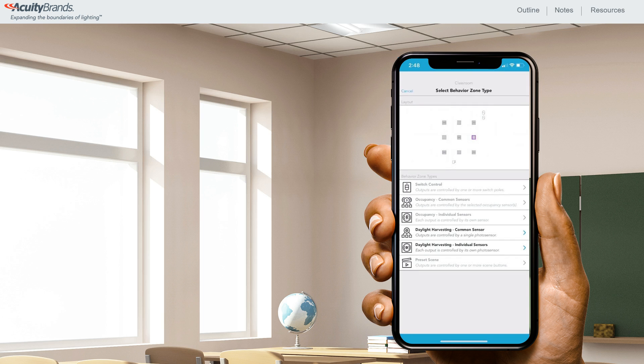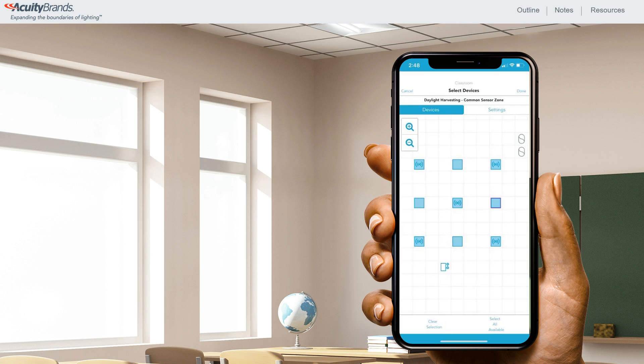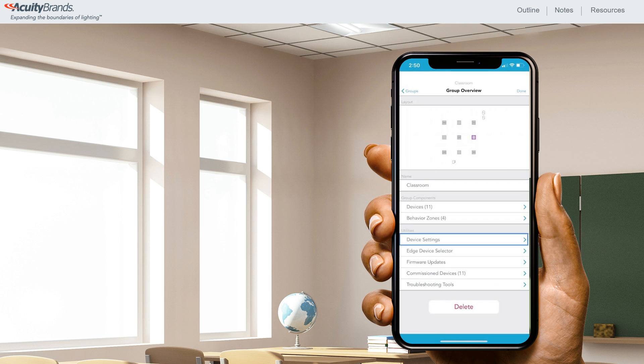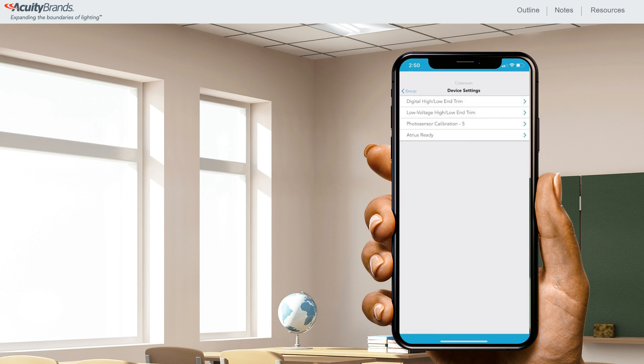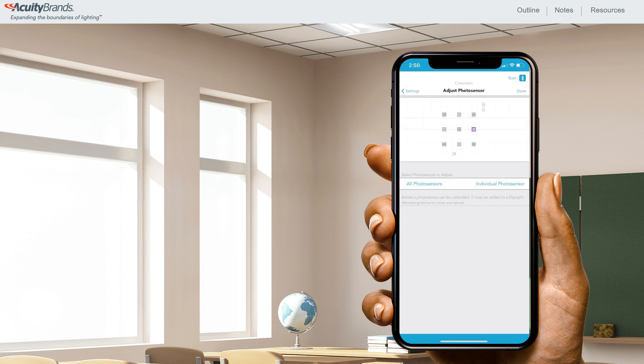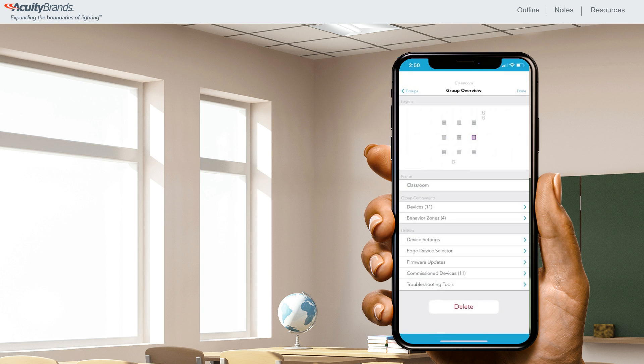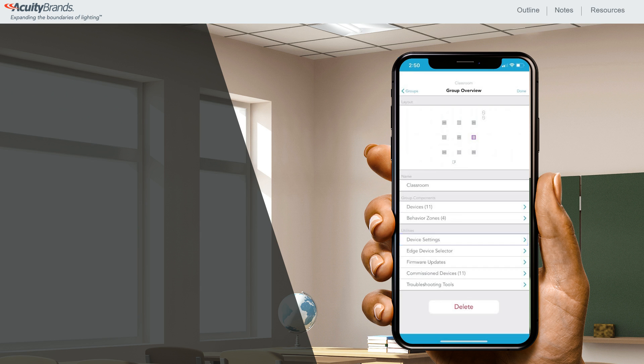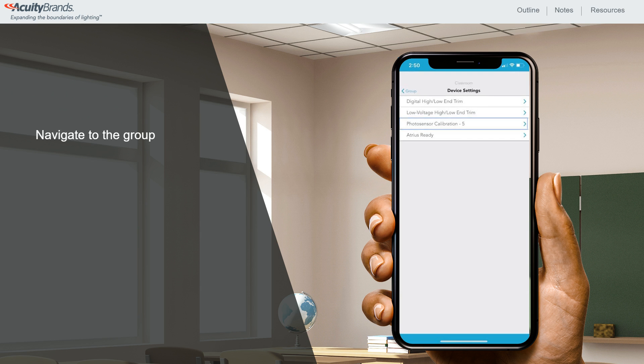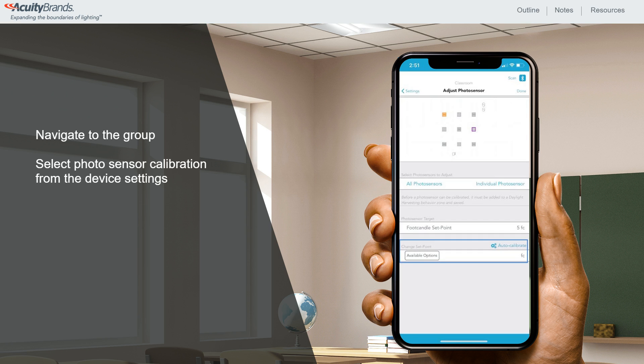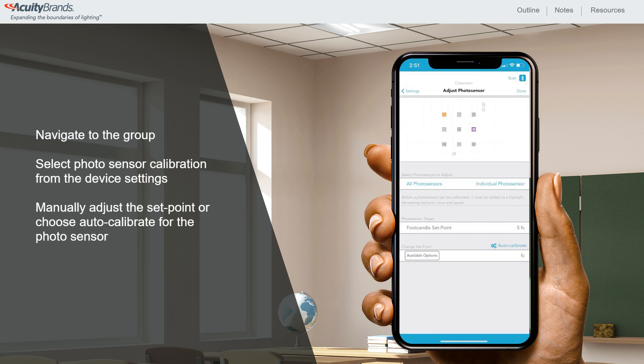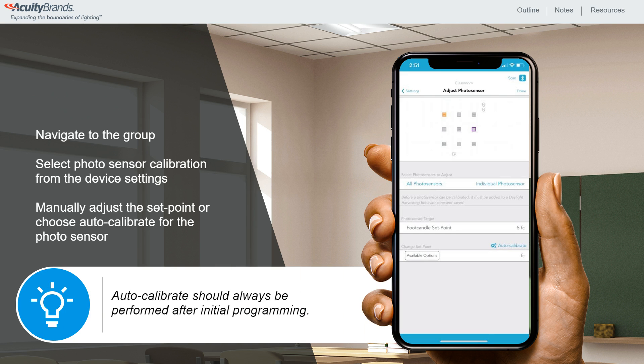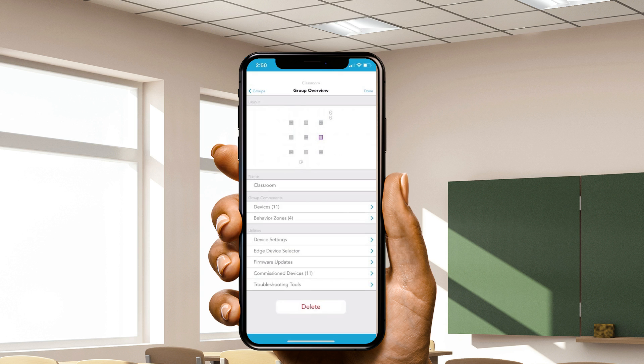Daylight harvesting behavior zones can be applied to any group with at least one sensor. These specific set points must be calibrated after the programming has been sent to the fixtures. This can be done by navigating to the group overview screen, selecting Device Settings, and selecting Photosensor Calibration. To calibrate daylighting, navigate to the group, and from Device Settings select Photosensor Calibration and manually adjust the set point or choose auto calibrate for the photosensor.